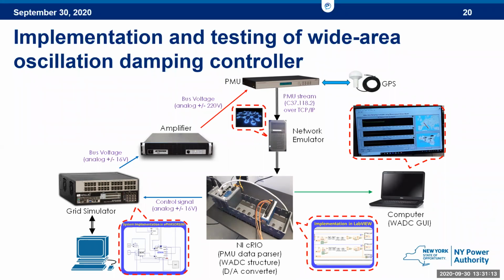The key idea is that this controller receives PMU data from multiple locations on the grid. At the beginning of the project, there was an initial design using a small-scale test bed. The idea was to demonstrate this on the New York State grid system as well as the Terna system, which we did earlier this year, in January, bringing the controller into our lab. We ran hardware-in-the-loop simulations of our grid and the Terna grid, using actual PMU devices, streaming data to a PMU device, which went to the controller, which then sent control signals back to specific actuators on the grid, demonstrating that it can damp the oscillations.